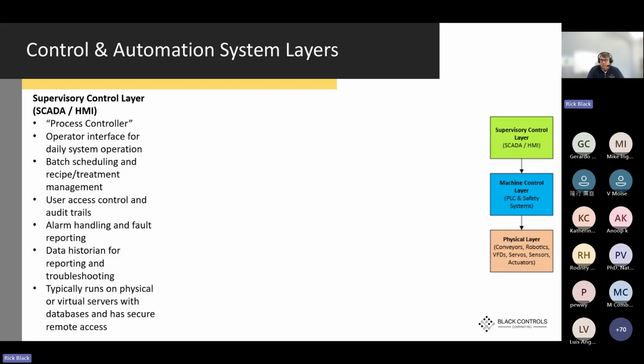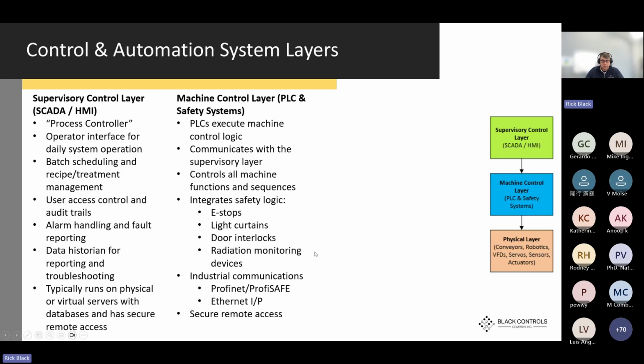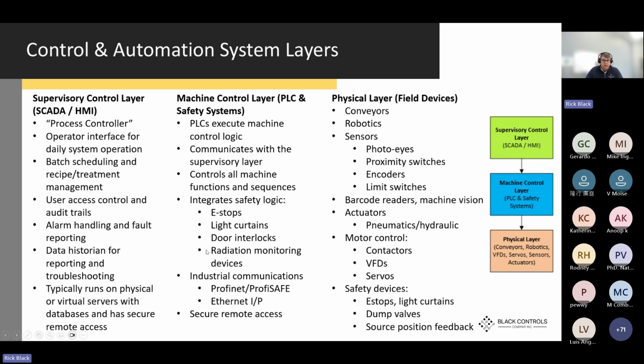Most modern irradiation systems follow a layered controlled architecture. Overseeing the whole system at the top, you'll have a SCADA or HMI layer, which provides operator interaction, batch scheduling, alarming, data history, things like that. Below that, you'll have a PLC and safety layer, which executes cyclical machine logic and enforces safety interlocks, things like e-stops, door interlocks, radiation monitoring devices. And continuing the trend, at the lowest layer is the physical layer, which includes things like conveyors, sensors, motors, safety devices, and field instrumentation. All these systems all work together, and they all need to support each other in order to produce a reliable, scalable, and highly maintainable system.